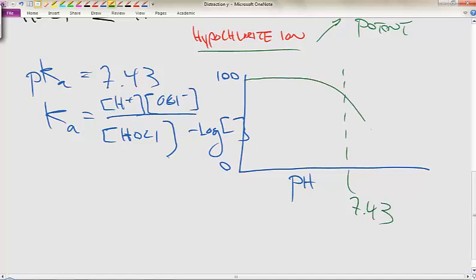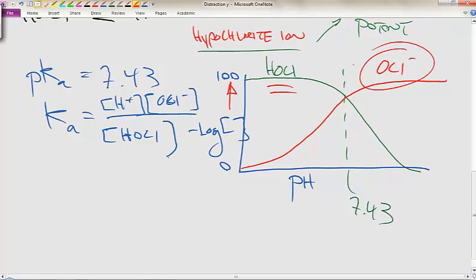We would get a graph with HOCl concentration here and hypochlorite ion concentration here. At pHs that are less than or equal to 7.43, the majority of what you would form would be the hypochlorous acid. That's what you want. At more alkaline systems or alkaline waters, you've got to be real careful. You're going to be forming this hypochlorite ion, and it's going to take a whole lot more free chlorine to disinfect correctly. Fortunately, most waters we treat are fairly circumneutral, pH about 7 or so, which would favor this hypochlorous acid in that system, which would be a very effective chemistry.